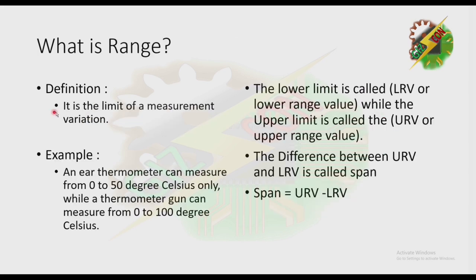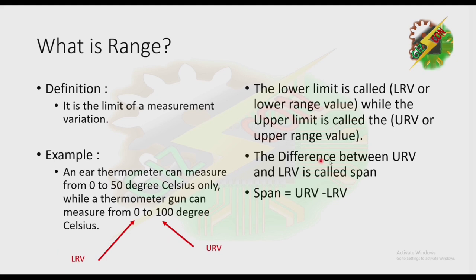What is Range? By definition, it is the limit of measurement variation. For example, an ear thermometer can measure from 0 to 50 degrees Celsius only, while another thermometer can measure from 0 to 100 degrees Celsius. The lower limit is called LRV or Lower Range Value, while the upper limit is called URV or Upper Range Value. The difference between URV and LRV is called span. Span is equivalent to URV minus LRV.